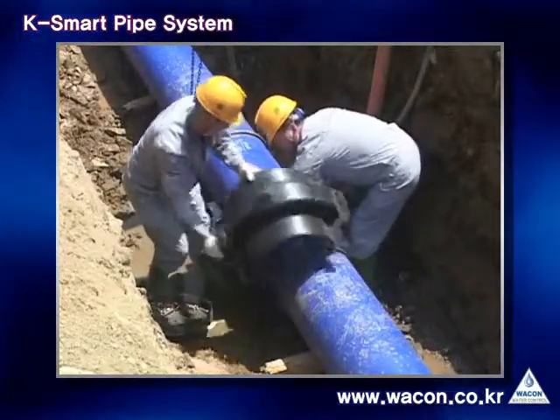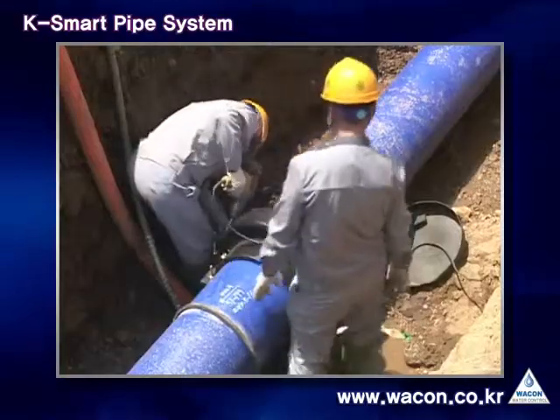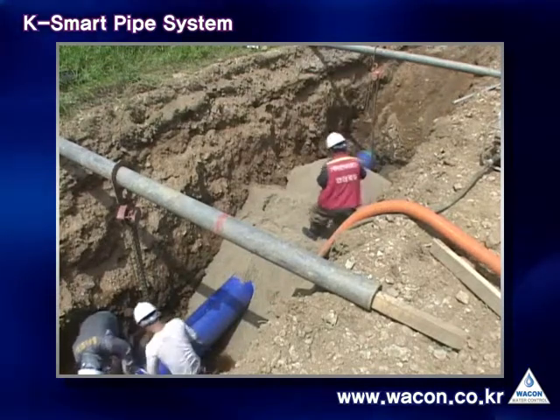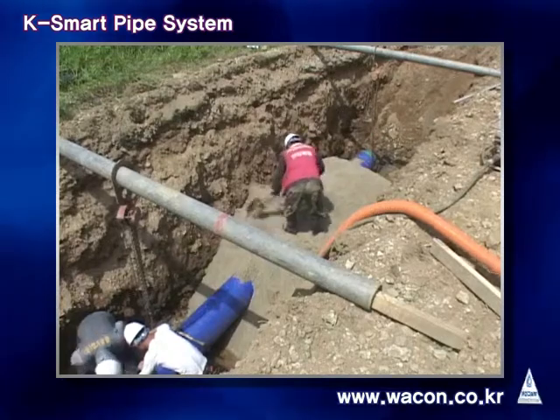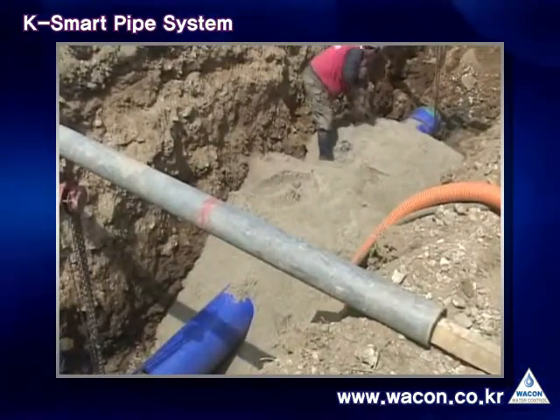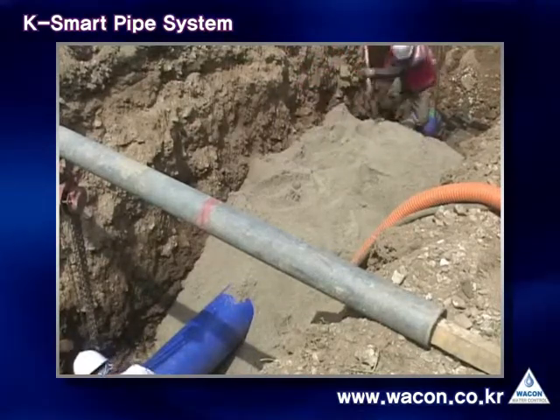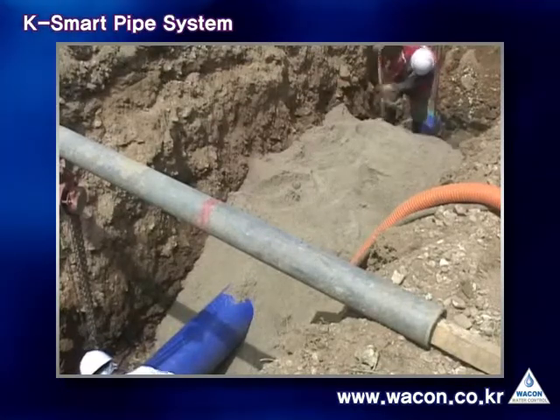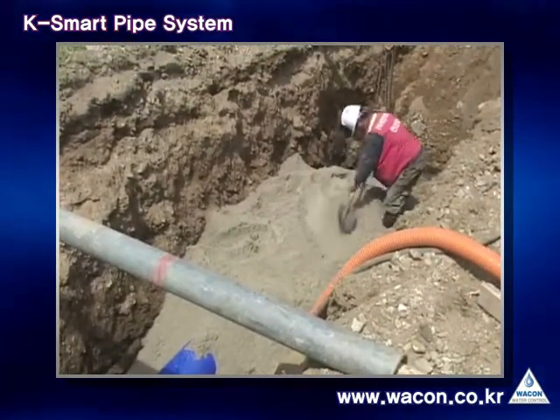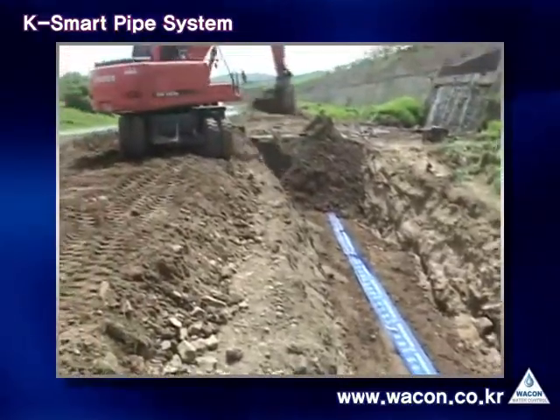Next, a hardcover is used to protect the connection point of pipes — it has two pieces. When assembling these, you must put the cover having an air vent on the top of the pipe. Now is the last operation, and this is the most important. Pipelines connected up until now should be well maintained without damage. If sharp objects such as stones or pebbles are thrown around the pipe body, the earth pressure will break the coating of the pipe, resulting in corrosion or cable breakage. These problems may not appear at the time of construction but may come out as time goes by. Therefore, fill up sand around the pipe body by more than 20 centimeters. If there is no sand, replace it with soft soil without sharp objects.